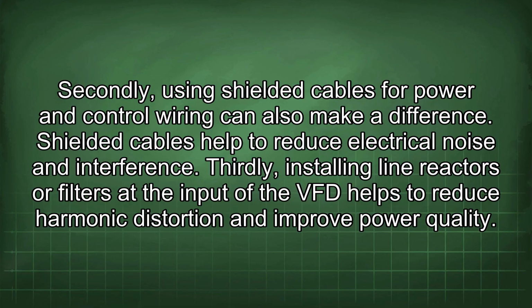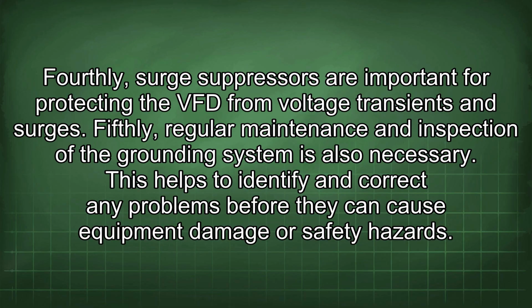Thirdly, installing line reactors or filters at the input of the VFD helps to reduce harmonic distortion and improve power quality. Fourthly, surge suppressors are important for protecting the VFD from voltage transients and surges. Fifthly, regular maintenance and inspection of the grounding system is also necessary. This helps to identify and correct any problems before they can cause equipment damage or safety hazards.